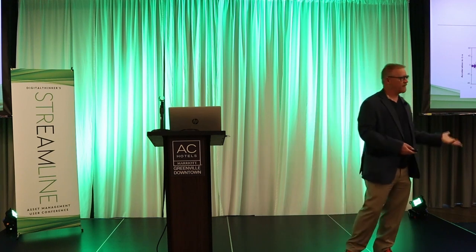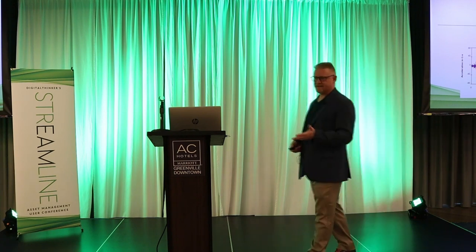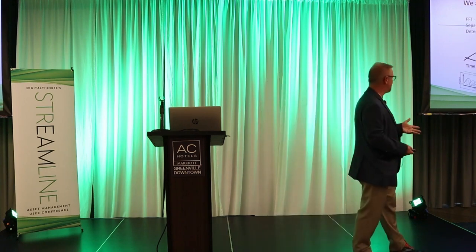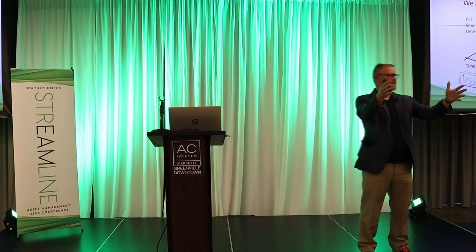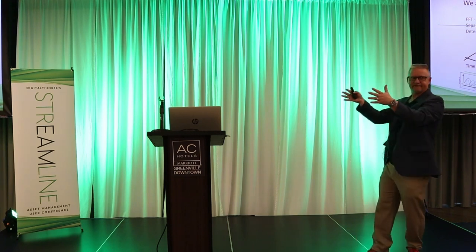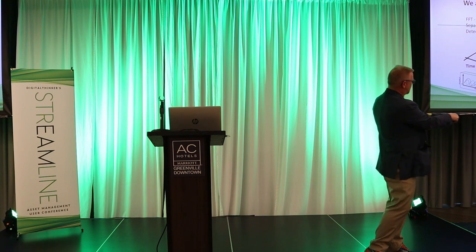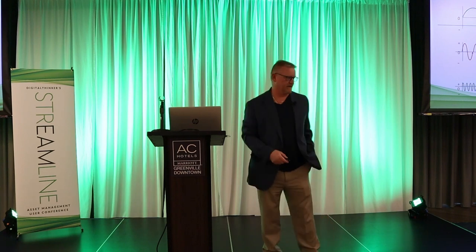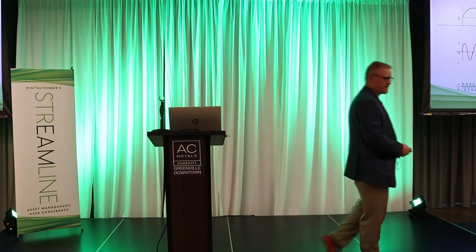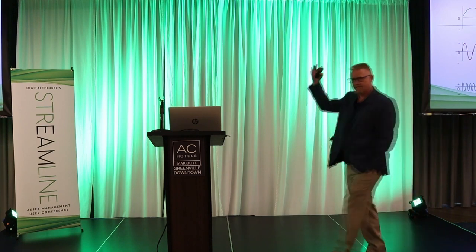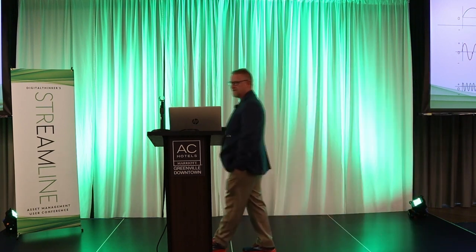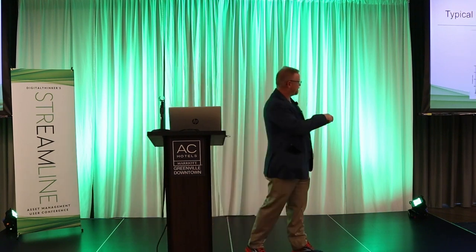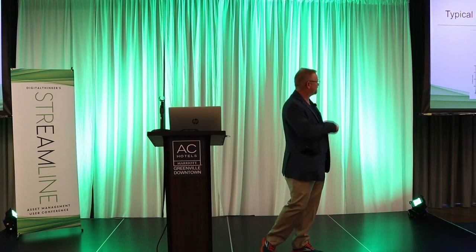And so the software associated with vibration analysis does a mathematical computation called a fast Fourier transformation. That fast Fourier transformation basically takes this time waveform and looks at it sideways. And when I look at it sideways, what I get are just some peaks. I get peaks at 1 times turning speed, at 4 times turning speed, and at 12 times turning speed. And I can see the amplitude of those peaks and how those peaks are interrelated. And vibration analysis simply takes a look at those peaks and makes some determinations.